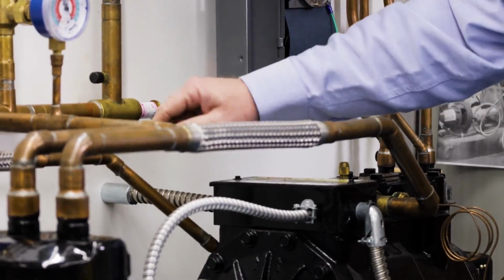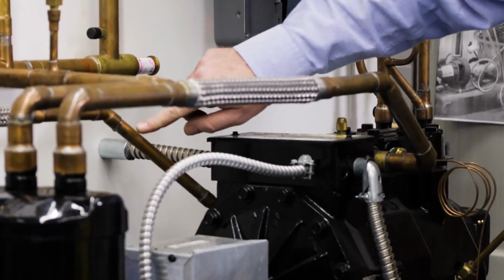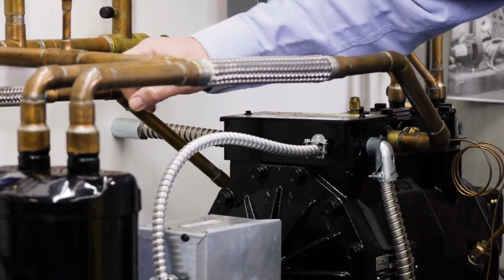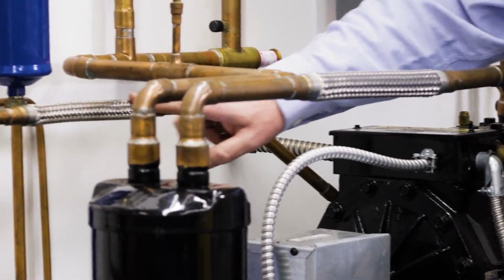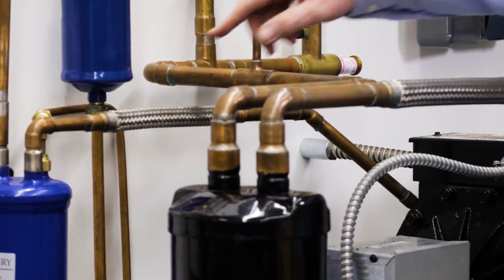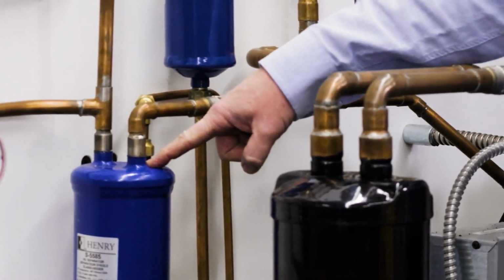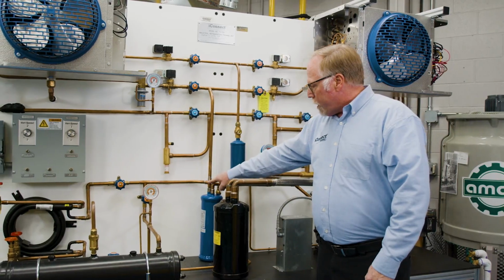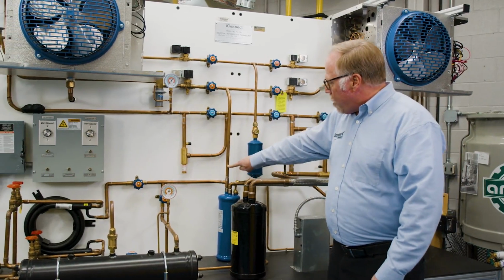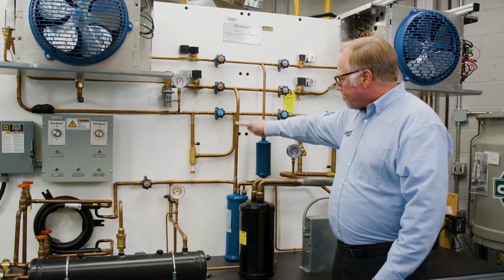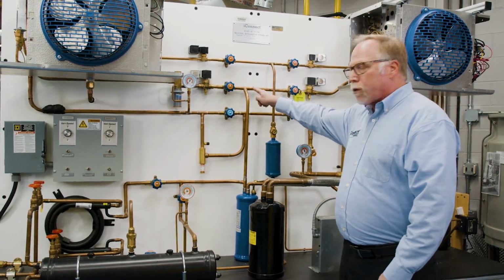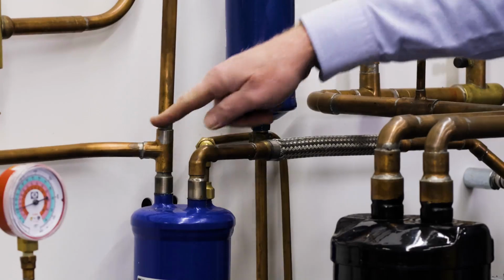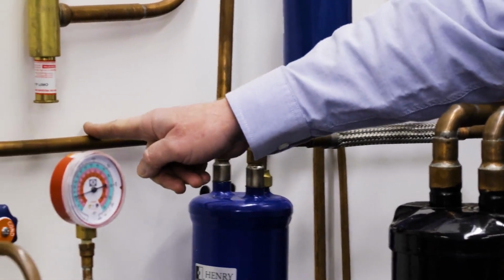So here we have our high pressure superheated gas. It comes out of the compressor. It goes through our vibration eliminator line, goes into our oil separator. It leaves the oil separator. Now it does not go up this line yet. It's going to stop at these two valves. We'll talk about that in a minute. But we're going to head them over here this direction.